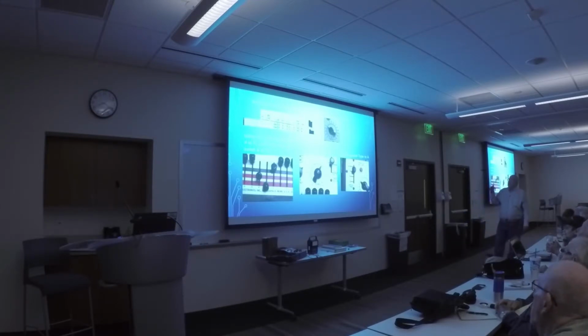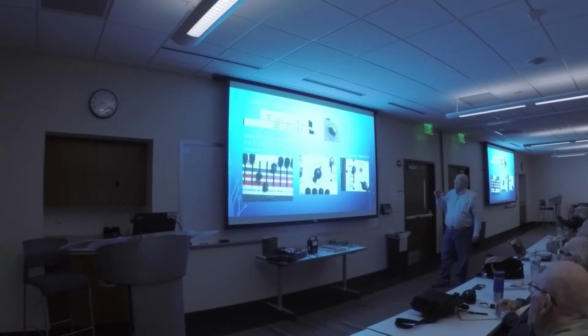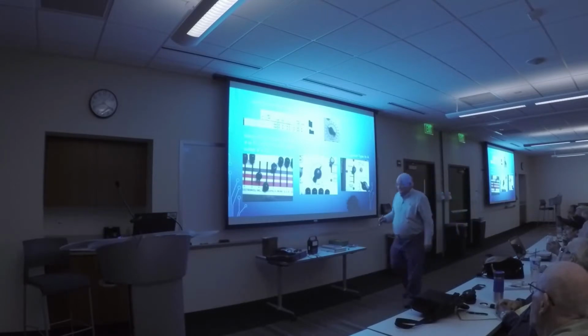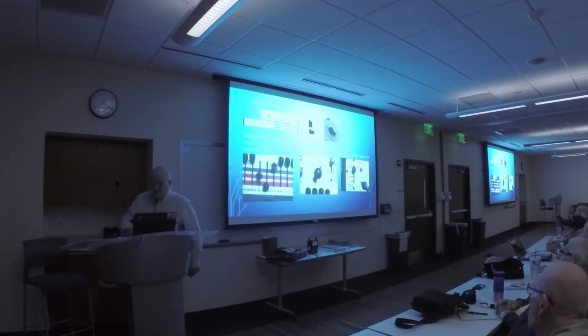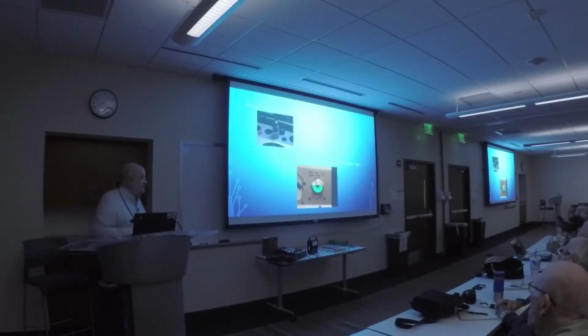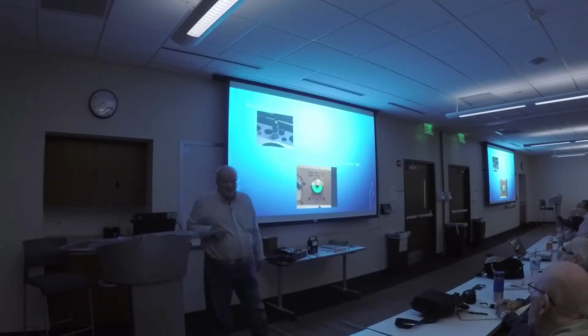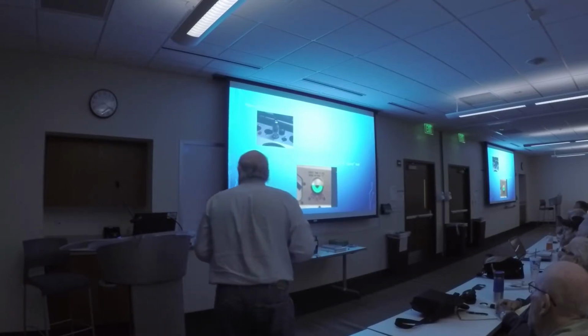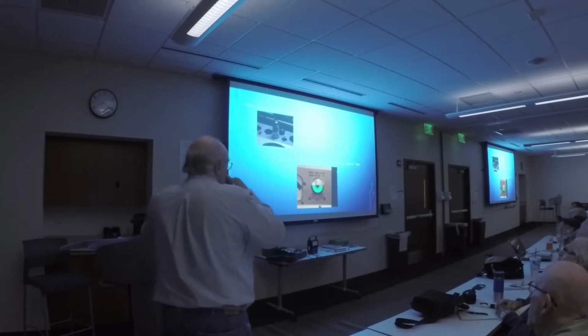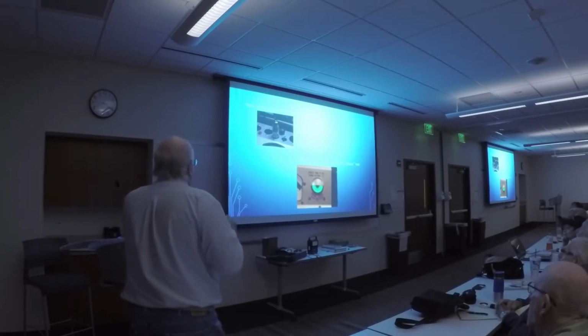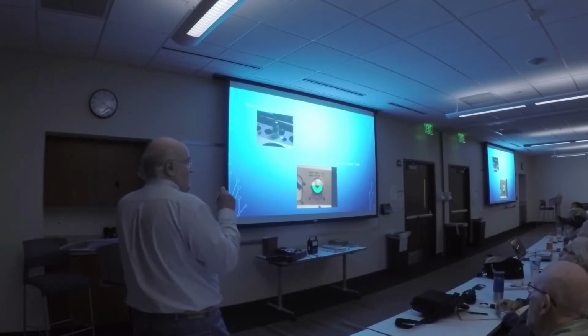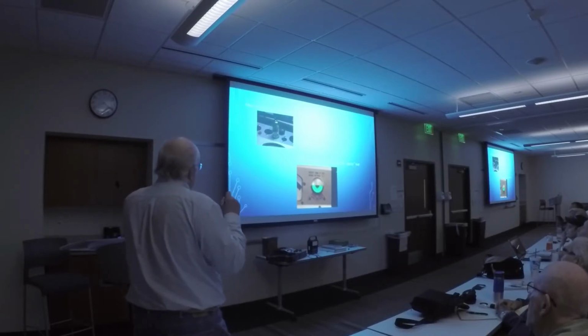So anyway, we set the filament voltage to 6, and we're using the switches. We set 4 here to the F1, the 5 to the F2, and the 6 to the Q. Then we set the load to 60. Then we set the special type to A. Okay, so you plug the tube in and you let it warm up a little bit, because it's a tube. It's got to warm up. It's got a little heater inside of it. And I swear that you could see that thing glow, but with the flash and the shutter speed, you probably can't see it. It's not glowing.